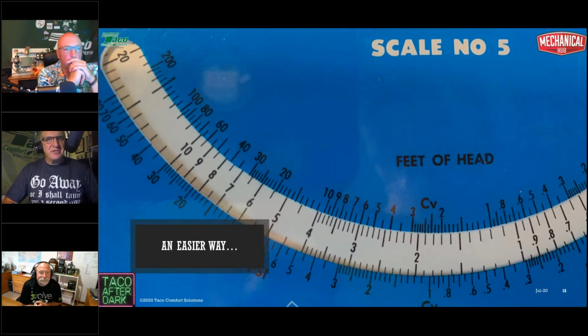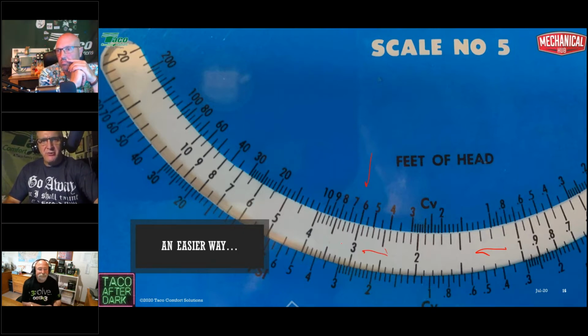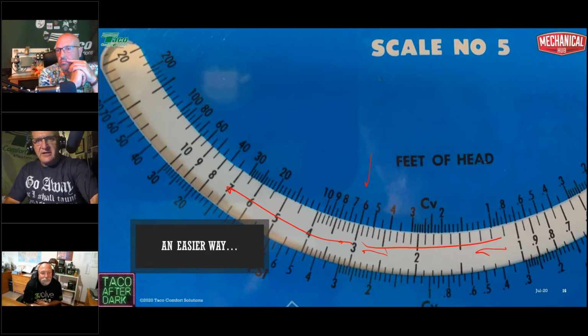The way you use this: on scale number 5 in this white window, it's a big adjustable wheel. You align your flow with the head that you know. So I know 3 gallons a minute, and I know 6 feet of head. Once those are lined up, all the math is done for me. If I go this way, I find out what the head is at different higher flow rates, and if I go this way, I find out what the head is at lower flow rates.